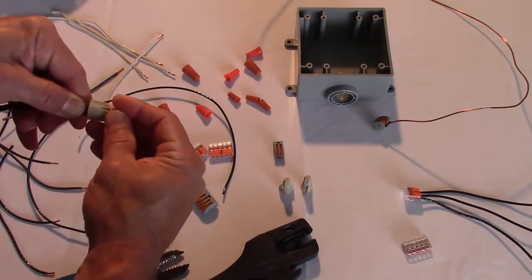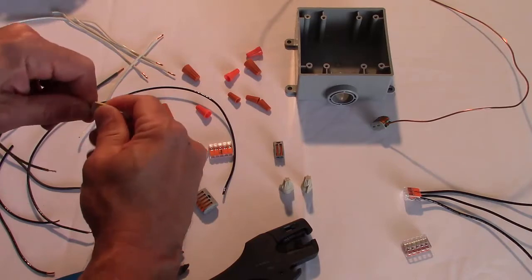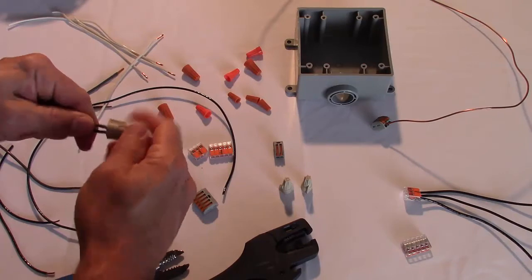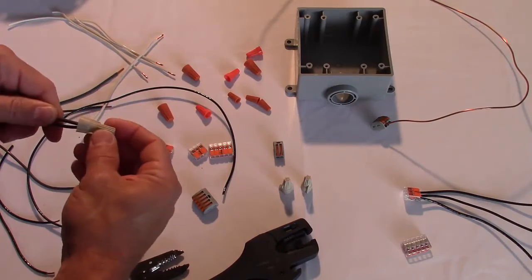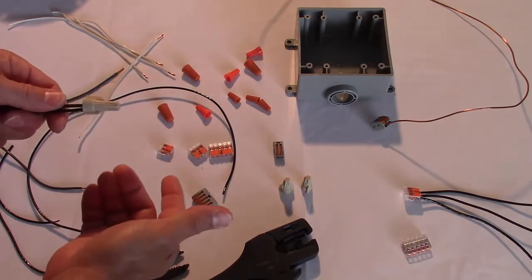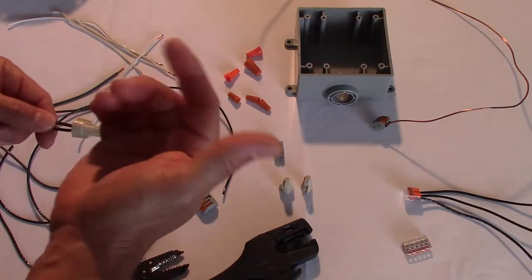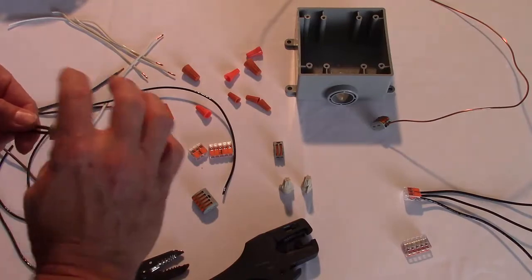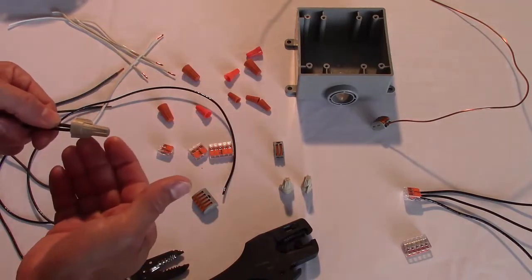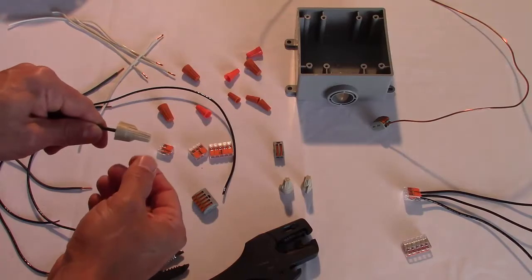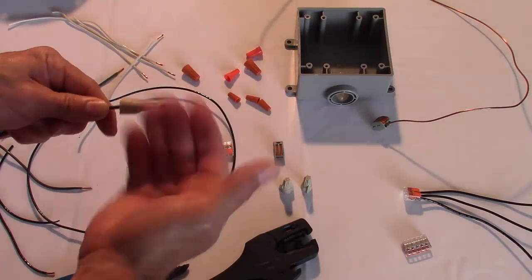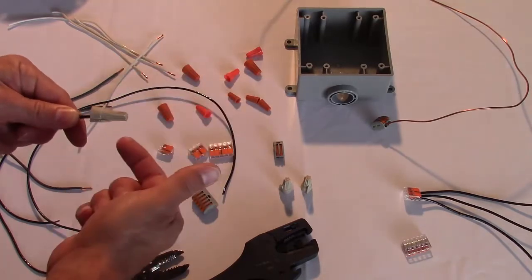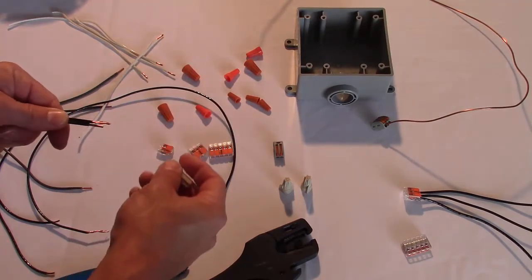If I have one that's a little bit closer to the same length, am I inserting it first? And then when you push in to ensure the connections are being made as you're twisting, the solid conductor can slide up and things like that. With the different types of conductors, it's one thing to consider how are they going to connect together when I start this twisting action. If I have a solid conductor and a stranded cable connection conductor, what's going to happen is as I start this twisting action, I'm going to start twisting and damaging the stranded connections on here, the stranded conductor itself.